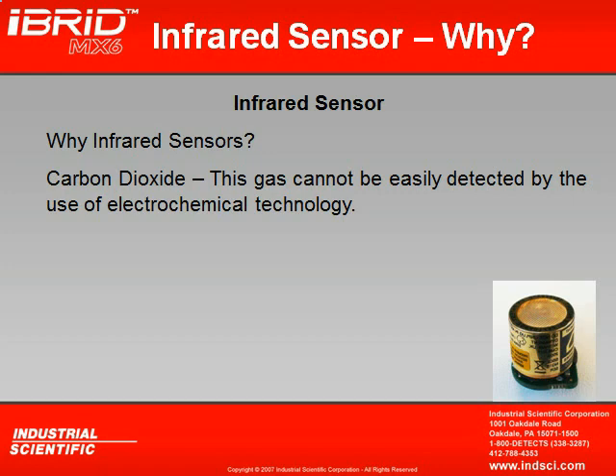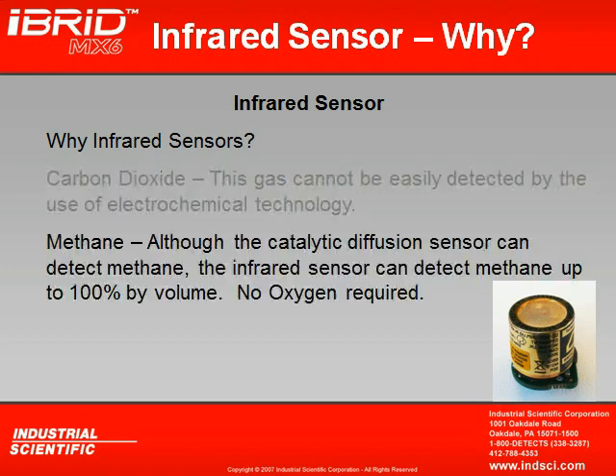And for methane, well, we know that the catalytic diffusion sensor can detect methane, but if I want to detect methane up to 100% by volume, I can't use the catalytic diffusion sensor because, remember, it needs at least 10% oxygen. So if I want to detect methane up to 100% by volume, naturally there's going to be no oxygen. Therefore, the infrared sensor becomes indispensable.